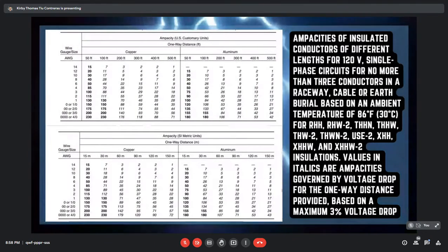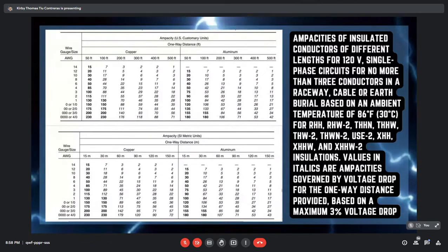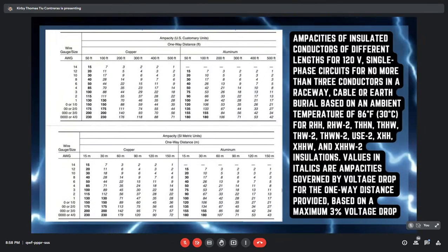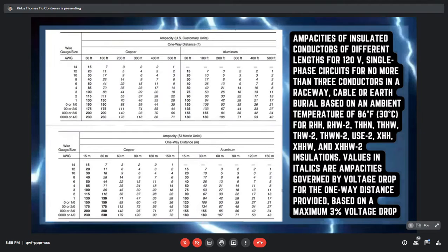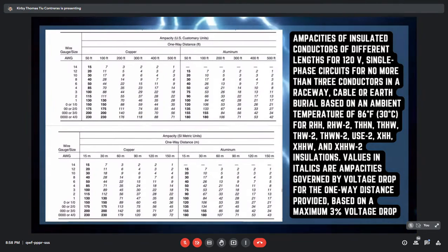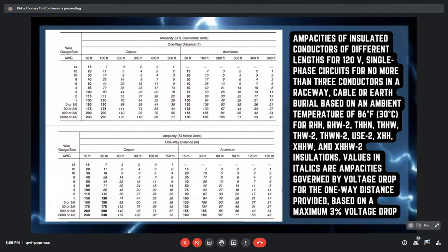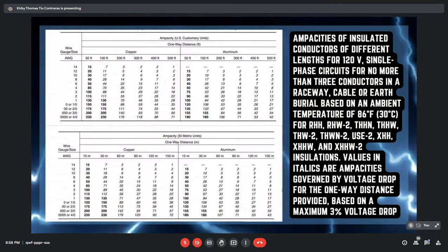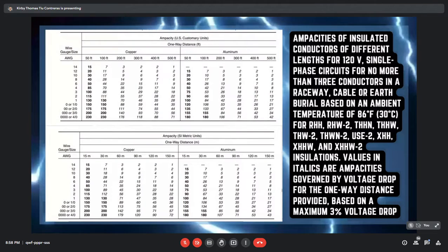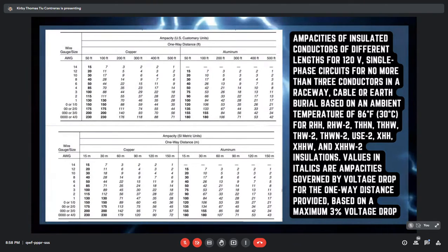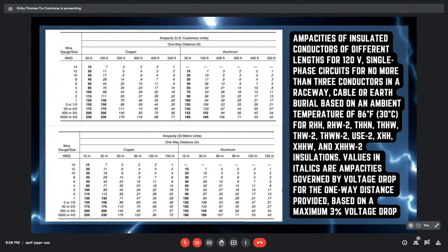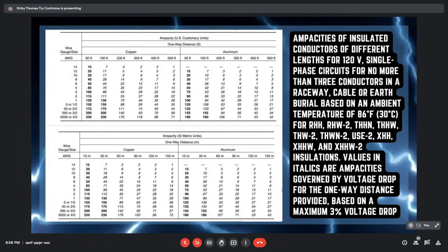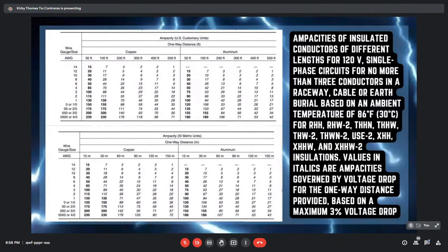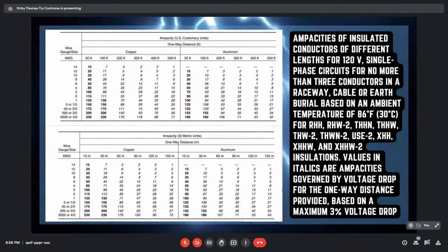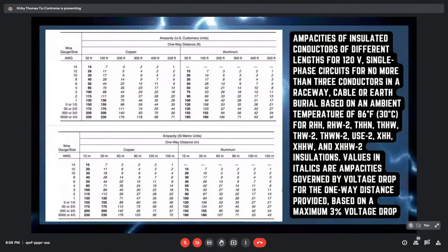So for example, a number 8 AWG size with a one-way distance of 200 feet has an ampacity of 9. And for aluminum, at 300 feet, a number 8 AWG conductor has an ampacity of 6. So next.